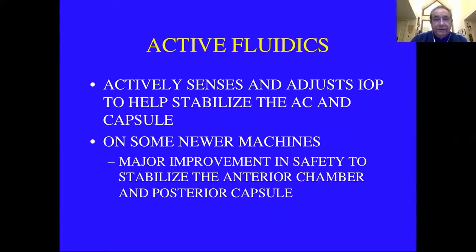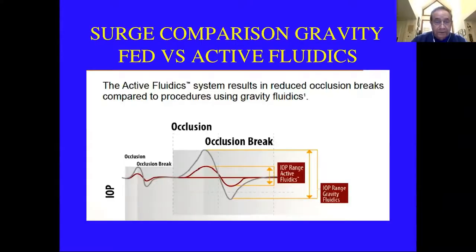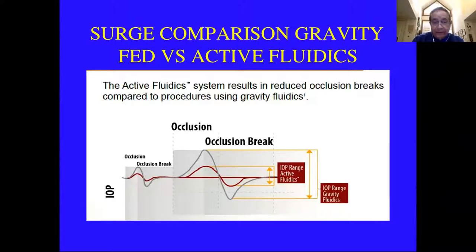Some newer machines have what is called active fluidics. Instead of just depending on bottle height for flow in, it actively senses and adjusts the intraocular pressure. This helps stabilize the anterior chamber and the capsule. It's a major improvement in safety because you get a much quieter eye and less likelihood of inadvertently aspirating the posterior capsule. The gray line shows what typically happens with a gravity feed system due to lag; the reddish line shows it's evened out with active fluidics, which senses eye pressure multiple times per second and adjusts.